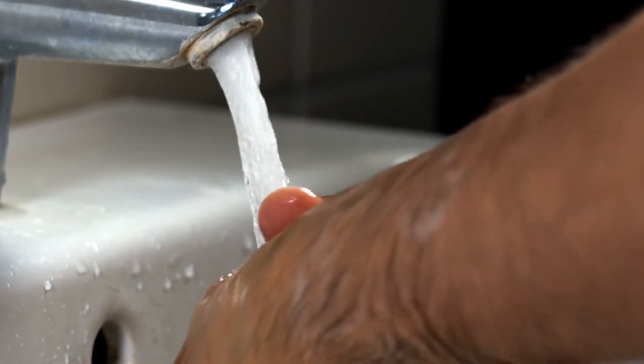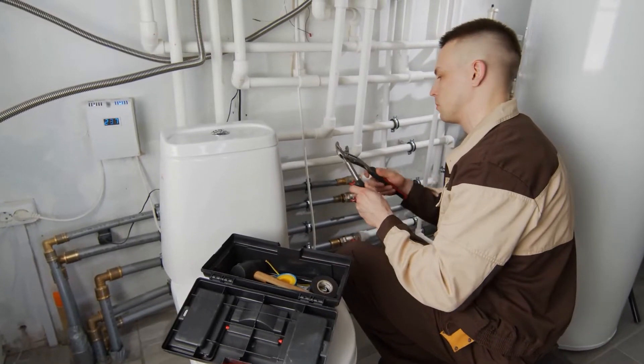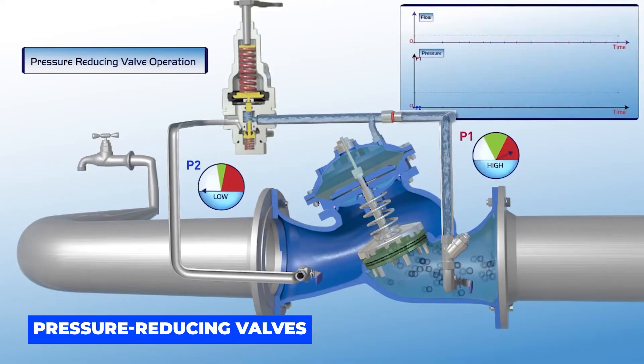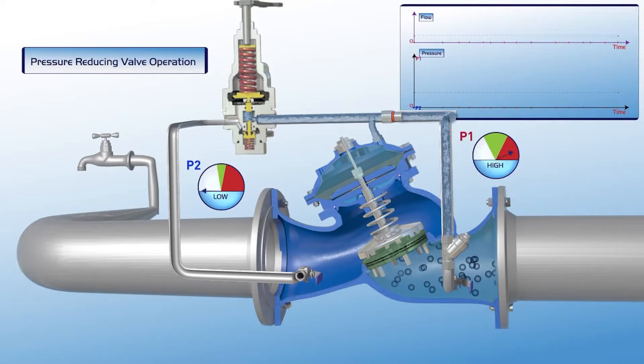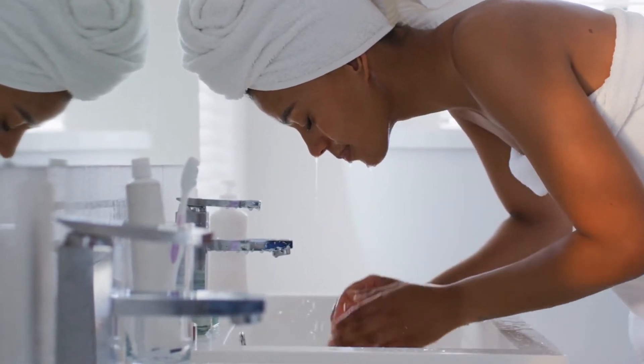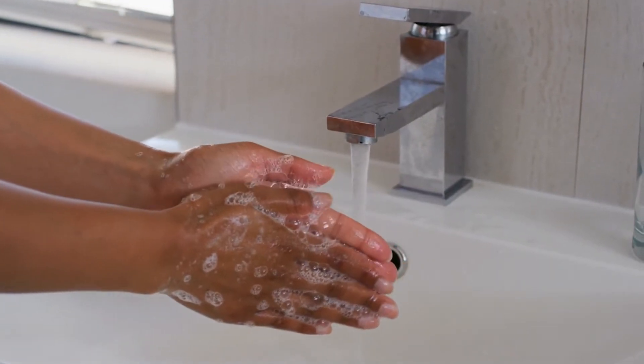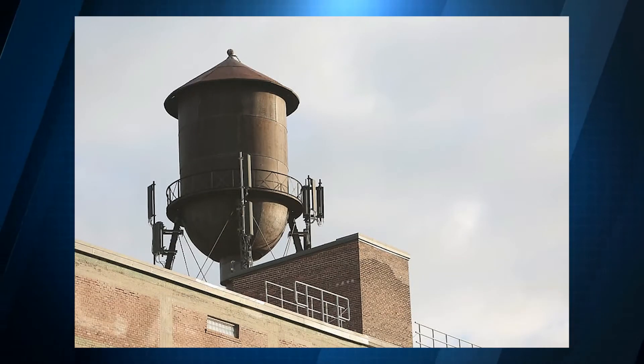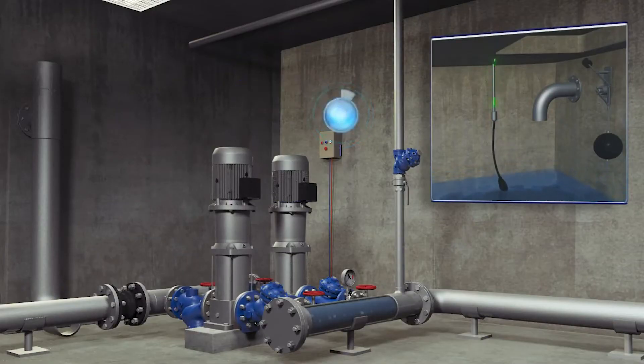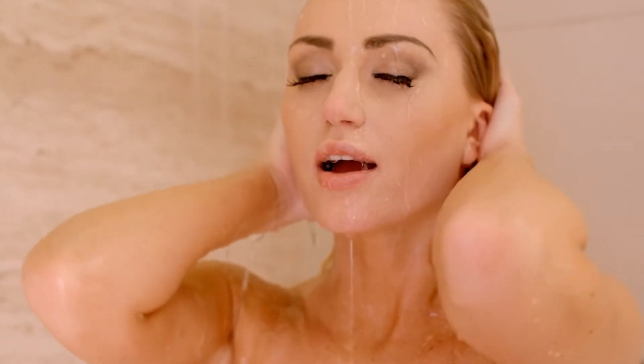Adding a pressure booster may allow the man on the 20th floor to receive an appropriate amount of water, but the woman on the first floor may be faced with a faucet that explodes each time she twists the nozzle on. Luckily, commercial plumbers have come to use pressure-reducing valves to avoid pressure rising above its maximum levels. This ensures that the pressure on the lower floors is somewhat equivalent to the pressure on the higher floors, finding an equilibrium that even Thanos would be proud of. Commercial plumbers simply use direct pumping systems and a mixture of pressure controls so that each resident has a similar experience regardless of where they're living in the building.